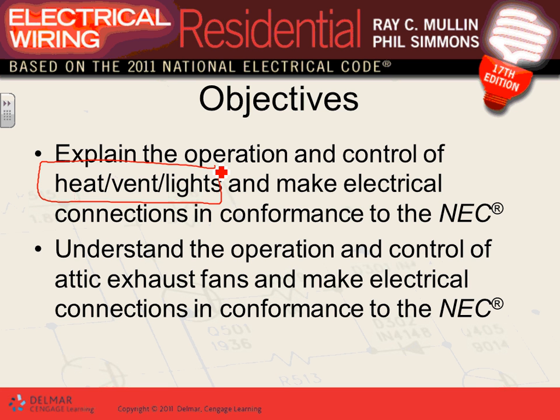So it's all a combo. If you have a combination like this, the only thing you need to do is provide a 20 amp dedicated circuit. Guaranteed. That's it. Because it has a heater in it and a fan and everything else. So what we do is we throw a dedicated 20 amp circuit on it. Done. Unlike the fan that you have in your bathroom: if you have just a fan, you can add the fan to your receptacle circuits. If it's a fan only. If it's a fan light, you can add it to your lighting circuit.